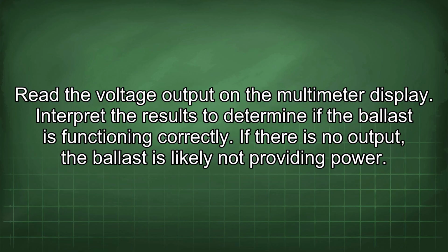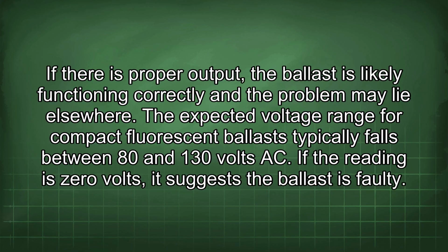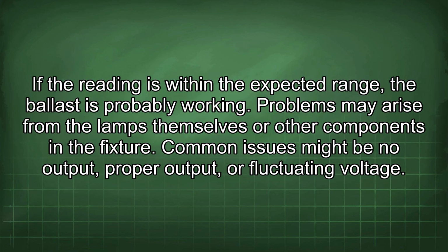If there is no output, the ballast is likely not providing power. If there is proper output, the ballast is likely functioning correctly and the problem may lie elsewhere. The expected voltage range for compact fluorescent ballasts typically falls between 80 and 130 volts AC. If the reading is 0 volts, it suggests the ballast is faulty. If the reading is within the expected range, the ballast is probably working.